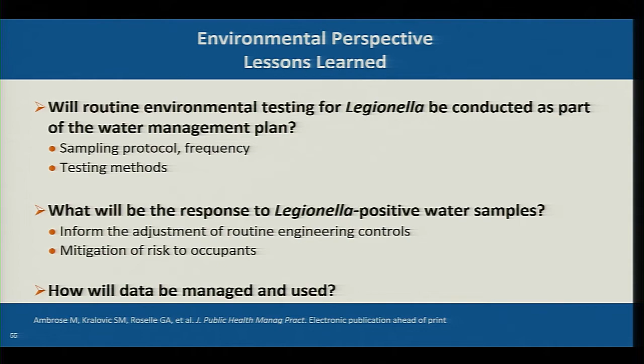There's little guidance or consensus available in the US for whether routine testing of potable water systems for Legionella should be done. If a decision is made to do it, include testing criteria in your written plans or procedures. Most importantly, have a plan for what you will do with the results. For validation of engineering controls, a key aspect of assessing Legionella results is to determine what they are telling you about how in control your system is. For example, if the extent of positive samples keeps increasing each testing cycle, that could indicate that Legionella are proliferating in the water system. Also important is determining if the results indicate that remediation of the system is necessary to reduce risk to building occupants. Ultimately, it comes down to managing and using the data being collected to inform decision-making.